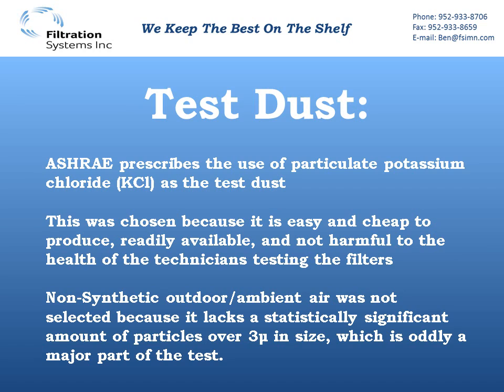ASHRAE prescribes the use of particulate potassium chloride as the test dust. This was chosen because it is relatively easy and inexpensive to produce, very readily available, and is not harmful to the health of the technicians if they were to inhale it.